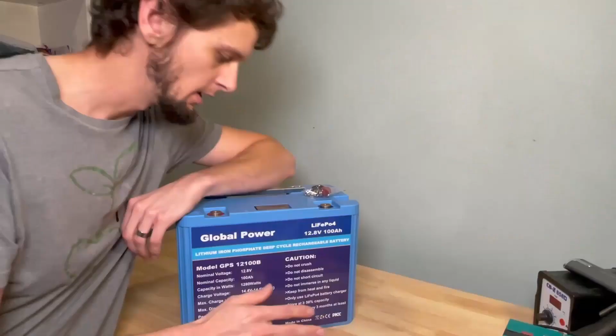Now, the things that I'm gonna test with this, I mentioned some of them. The fact that it's 100 amp hours, we're gonna check that. With lithium iron phosphate, you should be able to test to 100 to 105 amp hours on a brand new battery. So we're gonna do a discharge capacity test, and we're gonna test that it can do 100 amps continuous. So the idea is it'll be able to do 100 amps for an hour straight. So if we could at least get 20 or 30 minutes and things aren't shutting down, then we're good there.